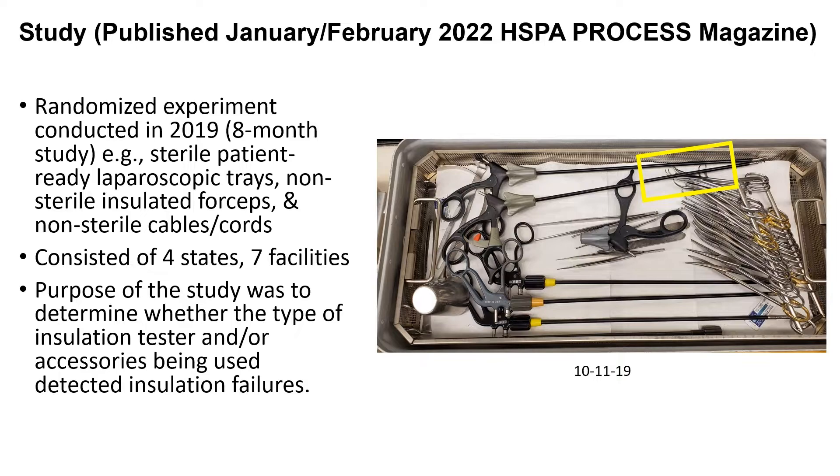In this picture, a tray was organized quite well — in one single tray — and it was opened in the department as a sterile tray ready to be used. But as you can see where it's circled, the towel clips are actually scratching against the insulation itself, causing damage and scratches, lesions on the side. So this tray, even though it looks great set up, was probably not the appropriate tray to use with insulated items — they would need to be separated.